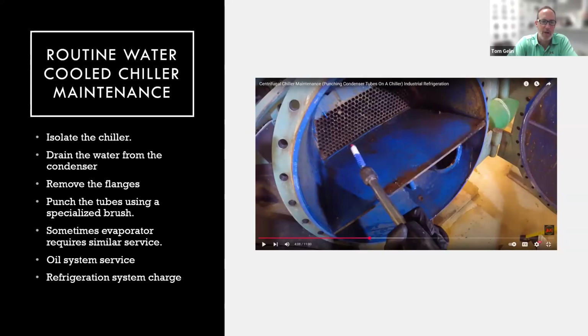And as well, we've got the same oil service — you may need to service both the condenser and the evaporator in a water-cooled system. But again, it's very mechanical, not particularly difficult. When I think about it, if there's a problem with the chiller, at least people know how to deal with it. If you have a problem with a VRF system, there's a lot of head scratching about what needs to be done and which software revision you have, et cetera. This is, as far as I'm concerned, pretty efficient and pretty straightforward.